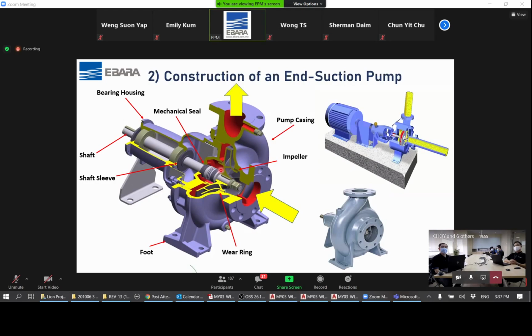the end. And this part is where the liquid or the water is contained, and the eye of the suction comes in, the water comes in through here, and as the impeller is churning, it actually creates that centrifugal force and expels the water out at a higher pressure. And a mechanical seal seals the wet part against the dry part. Okay, so the construction is pretty simple, and with that you can have a pump that is able to have a very big flow range within a certain, let's say, model or so.